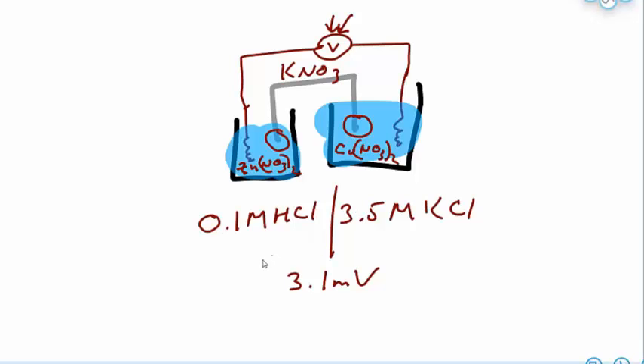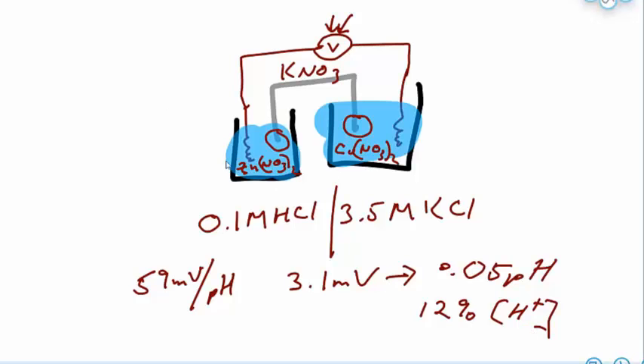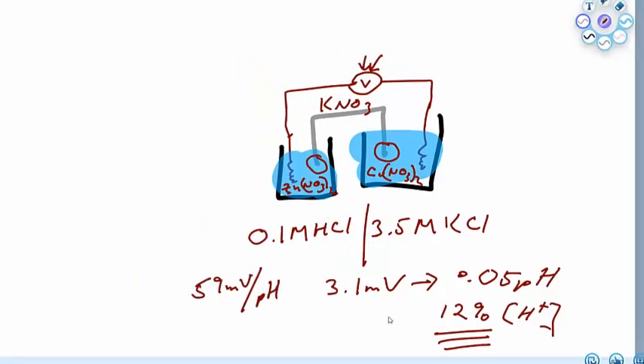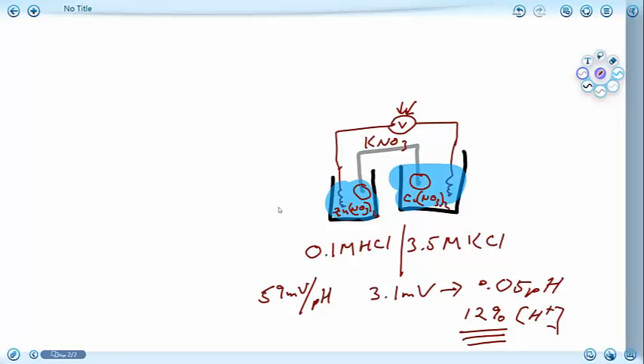If we are measuring the pH of the solution and maybe there's a junction potential of 3.1 millivolts because of the internal solution of the pH electrode, it has a pH response of 59.9 millivolts per pH unit. This 3.1 millivolts is going to result in an error of 0.05 pH units or about 12% of the hydrogen ion concentration. So we do need to be careful or be aware of junction potentials because they can contribute a significant amount of error to the observed measurement.